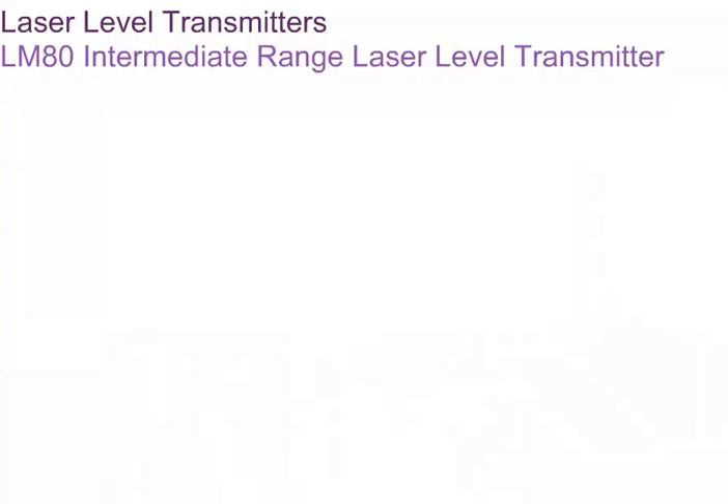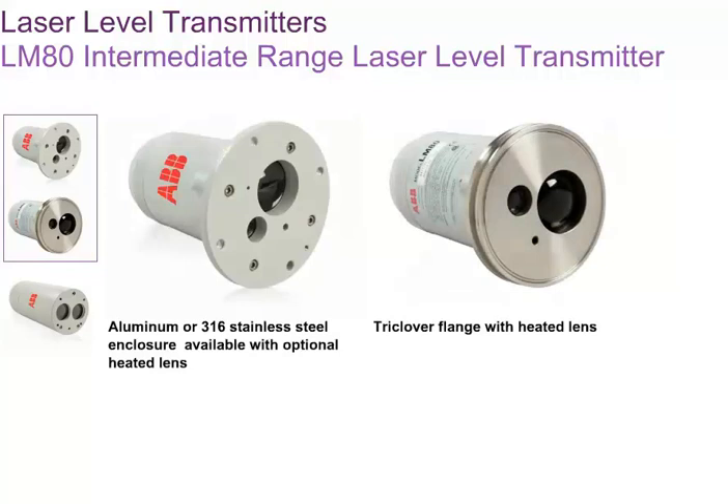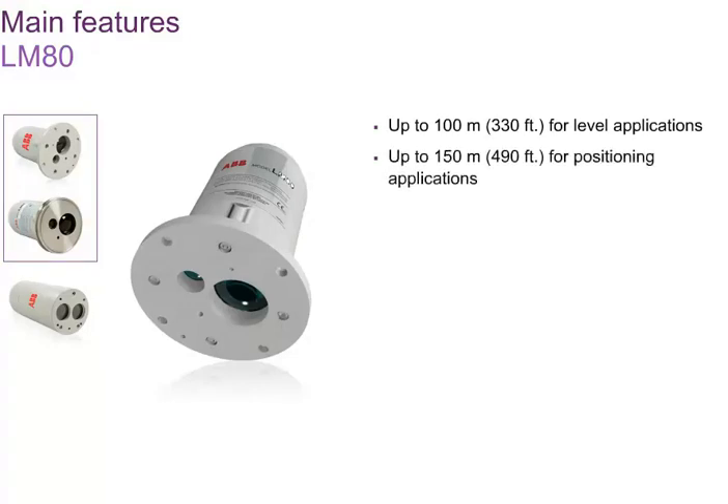The LM80 is applicable to most common applications. The LM80 laser level transmitter comes in different variants to suit specific applications. The heated lens is used to address condensation issues. The LM80 enclosure is optionally available in 316 stainless steel for environments where corrosion is a concern. The Triclover flange provides a hygienic interface for food, beverage or pharmaceutical applications. The LM80 has a working range of up to 100 meters for level applications and up to 150 meters for positioning applications with a reflector.